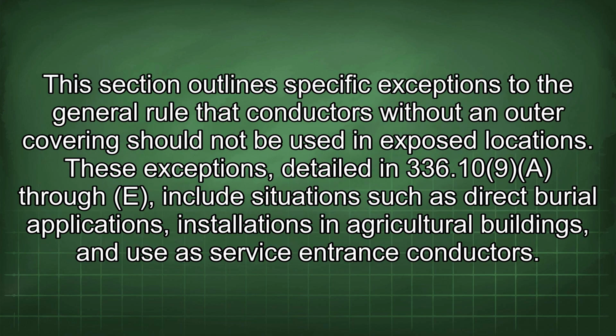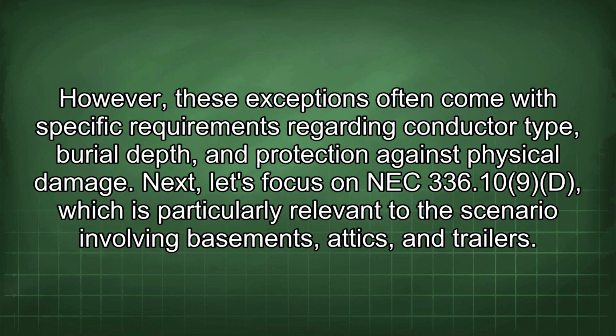This section outlines specific exceptions to the general rule that conductors without an outer covering should not be used in exposed locations. These exceptions, detailed in 336.10(9)(A) through (E), include situations such as direct burial applications, installations in agricultural buildings, and use as service entrance conductors. However, these exceptions often come with specific requirements regarding conductor type, burial depth, and protection against physical damage.